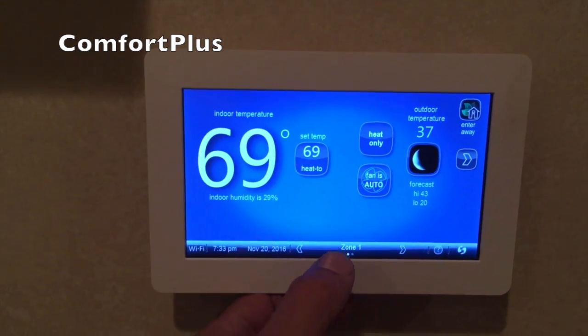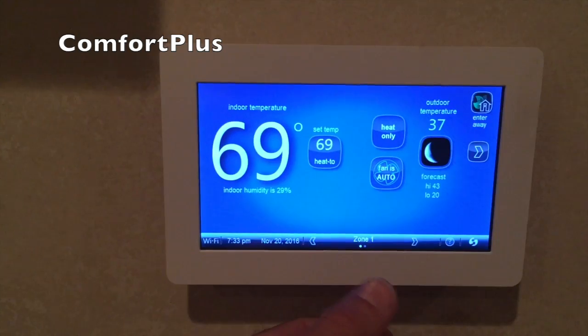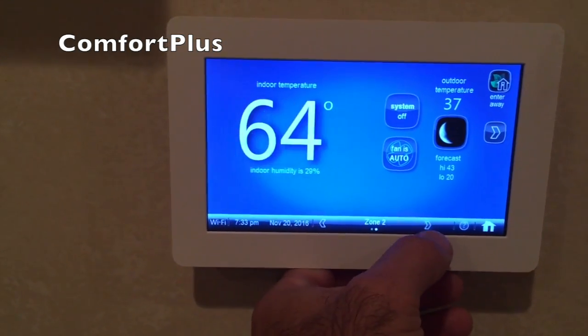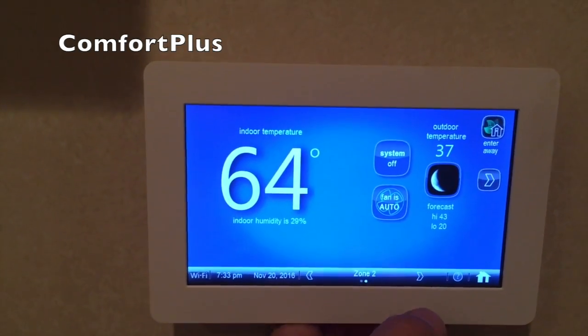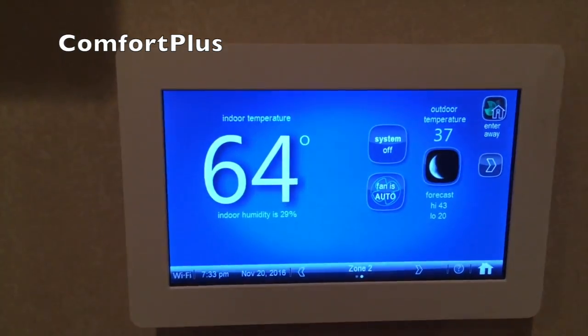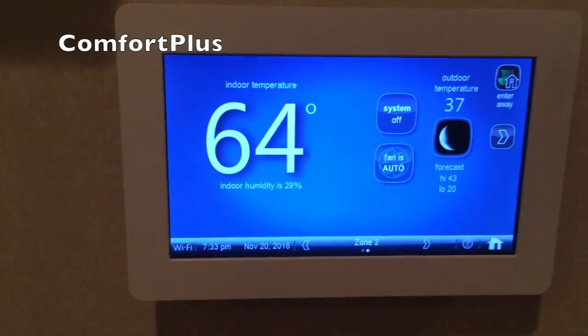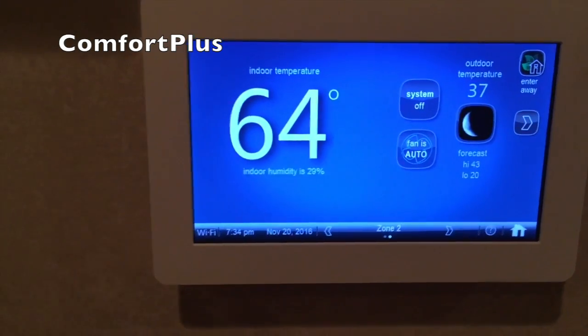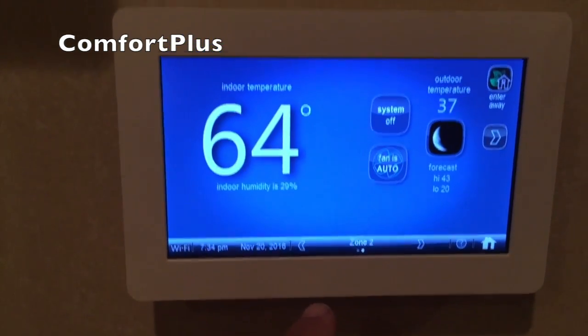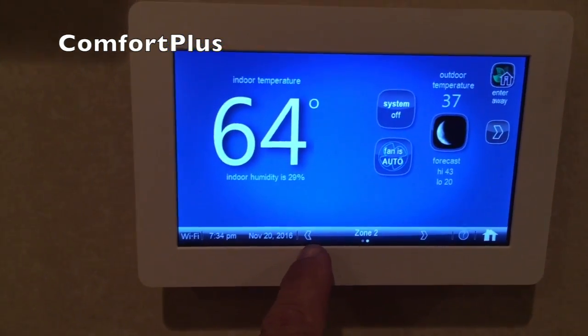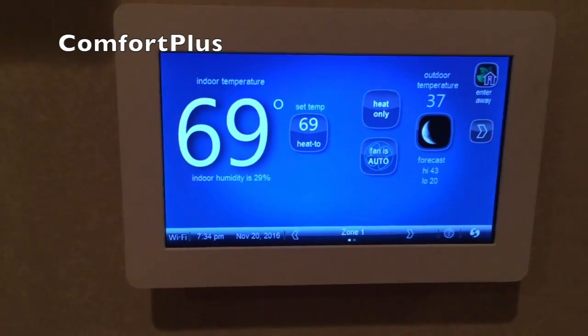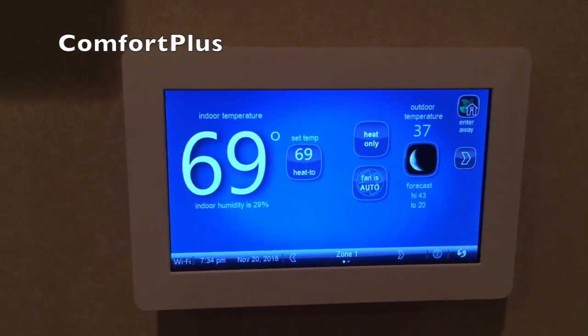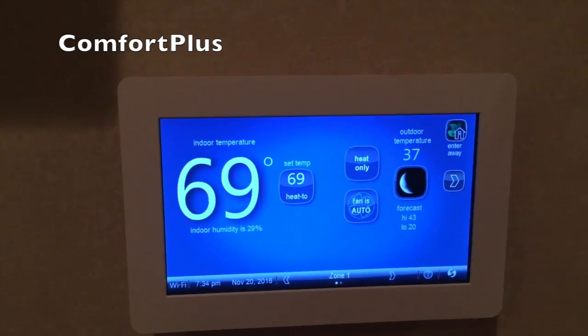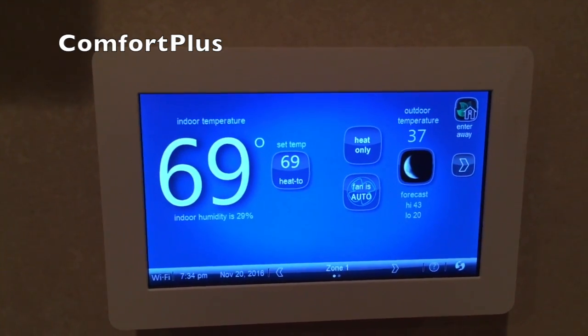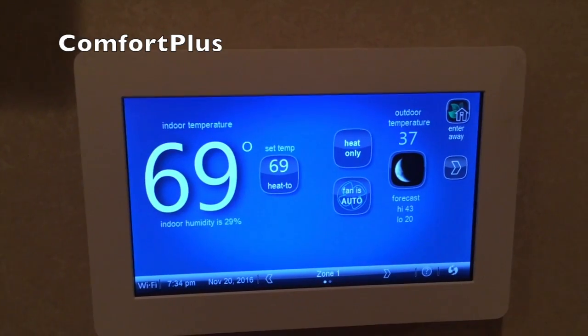You can see I'm keeping this main zone that I'm actually living in at 69 degrees. If I go over to the lower level zone, it's on 64 degrees because the system is off. Even though the house is very open, it still keeps a temperature difference between the two if I have that one zone damper closed. I'm convinced that this unit could probably heat my entire house if I could add the upstairs to a zone.